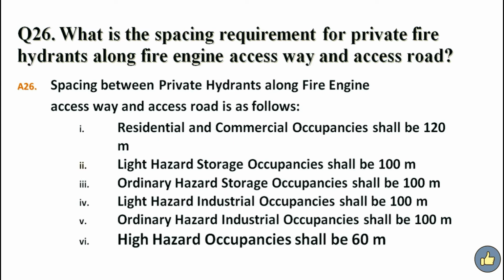Answer. Space between private hydrants along fire engine accessways and access roads are as follows. First, residential and commercial occupancies shall be 120 meters. Second, light hazard storage occupancies shall be 100 meters. Third, ordinary hazard storage occupancies shall be 100 meters. Fourth, light hazard industrial occupancies shall be 100 meters. Fifth, ordinary hazard industrial occupancies shall be 100 meters. Sixth, high hazard occupancies shall be 60 meters.